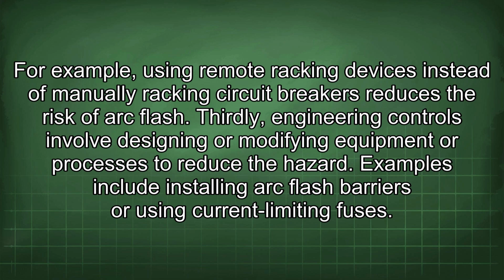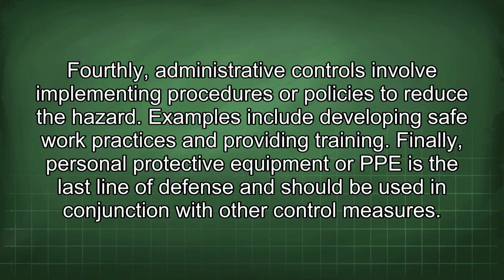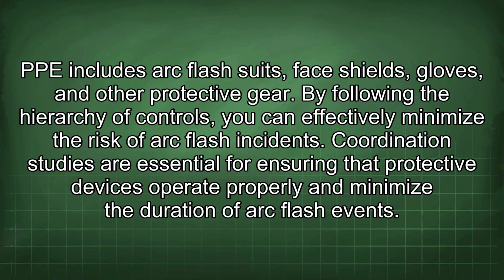Thirdly, engineering controls involve designing or modifying equipment or processes to reduce the hazard. Examples include installing arc flash barriers or using current limiting fuses. Fourthly, administrative controls involve implementing procedures or policies to reduce the hazard. Examples include developing safe work practices and providing training. Finally, personal protective equipment or PPE is the last line of defense and should be used in conjunction with other control measures. PPE includes arc flash suits, face shields, gloves, and other protective gear. By following the hierarchy of controls, you can effectively minimize the risk of arc flash incidents.